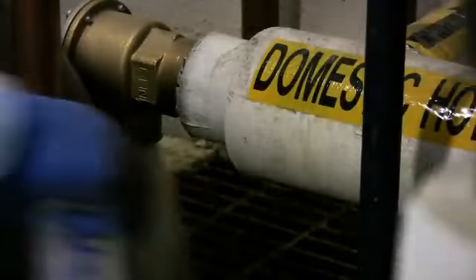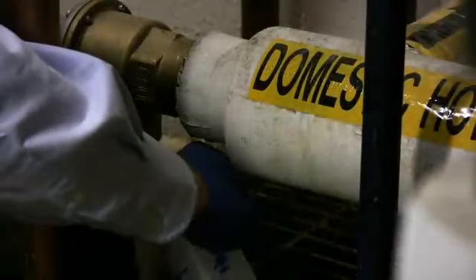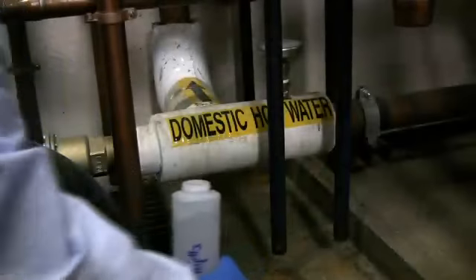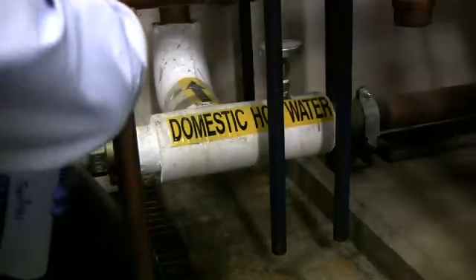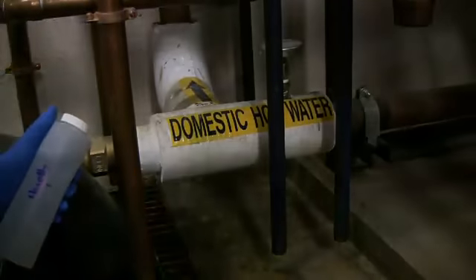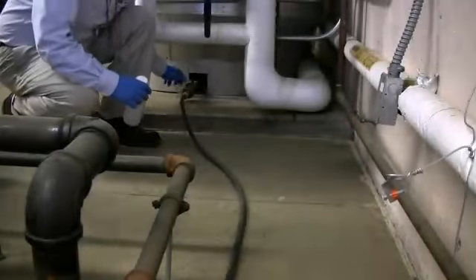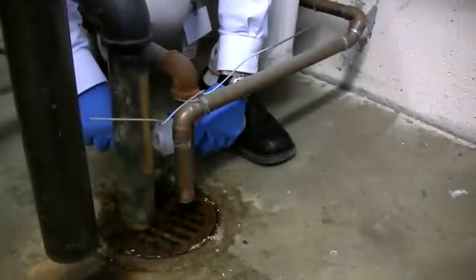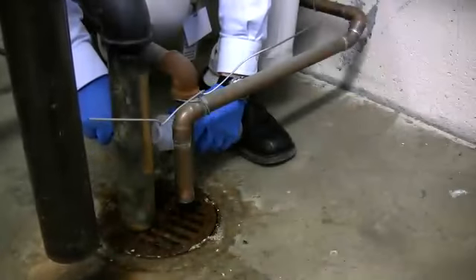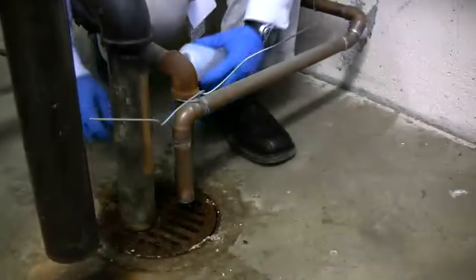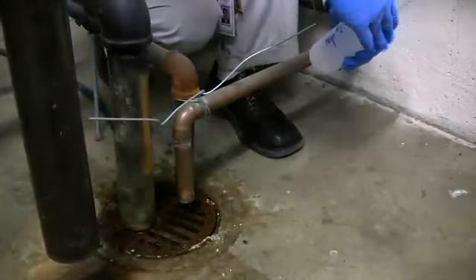Newer systems may have a valve that can be easily accessed to take the sample from, while some older systems may require the use of blow-off or drain valves that can be more challenging. This procedure is the same for dedicated valves and blowdown valves or drain lines. Once a bottle is filled, securely fasten the top and verify the information on the bottle matches the chain of custody and prepare the sample for shipping.